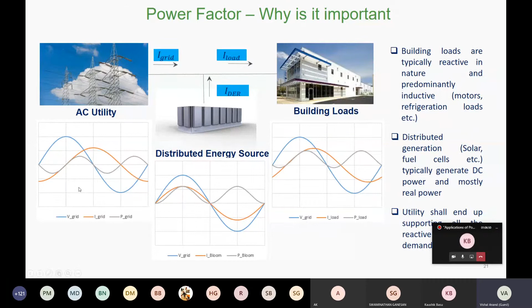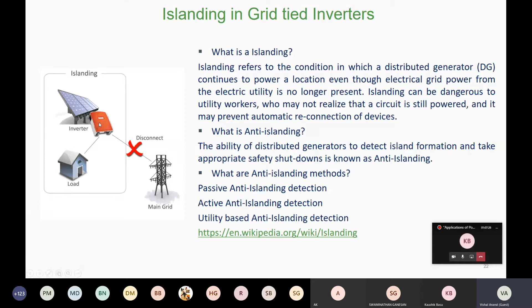The last topic I want to discuss today is islanding. Because we have more distributed energy resources, what is islanding? Islanding refers to the condition in which the main grid is lost, but the grid tie inverter sees the reflection of its own voltage on the load as the actual grid and continues powering. This is not acceptable, because somebody might think the grid is not available, but actually the grid might be live. So the inverters have to know this, detect it, and disconnect themselves.